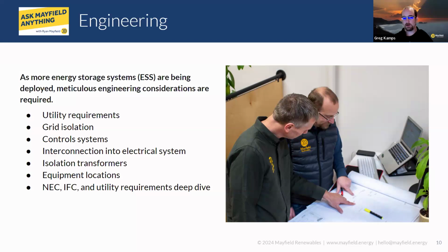It basically gathers a lot of different information from different points in the system, like CTs on the solar production, CTs on the panels and what the loads are, CTs on the generator, CTs on all the different assets, and basically uses that information to make decisions, to try and control the system in a way to keep the battery state of charge in a good point and make sure it's interacting with the other systems in the building effectively.